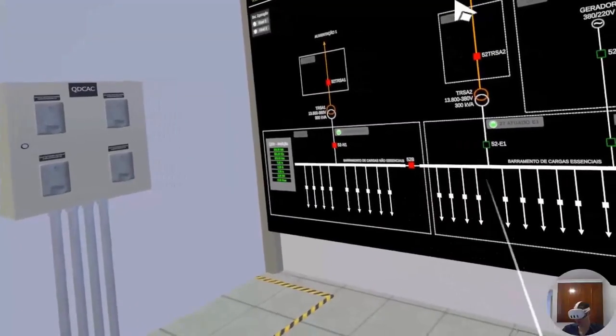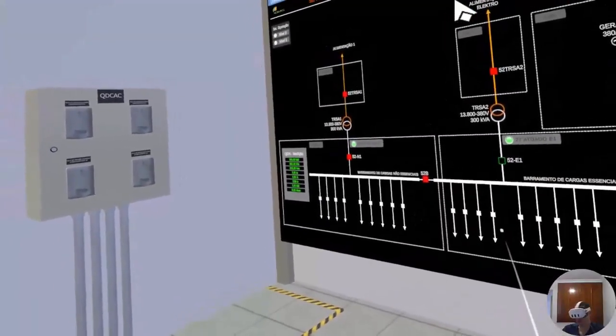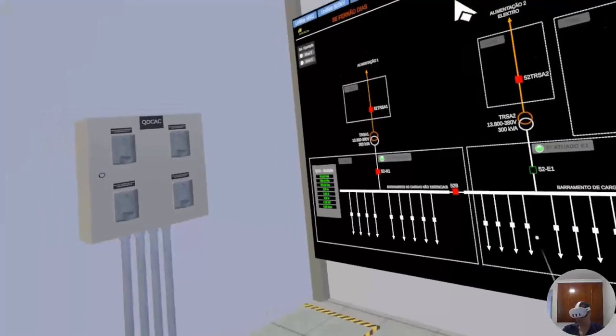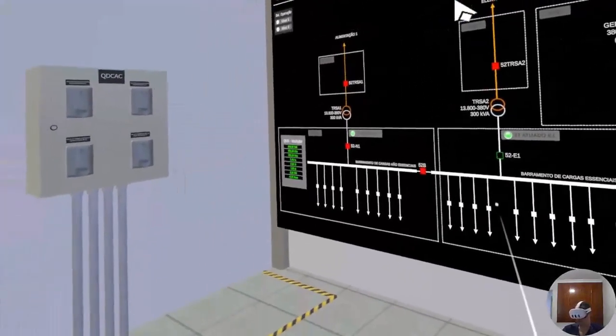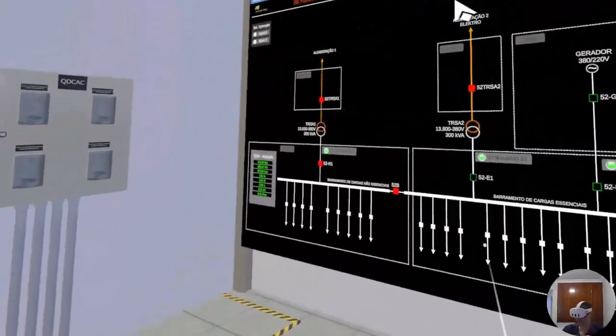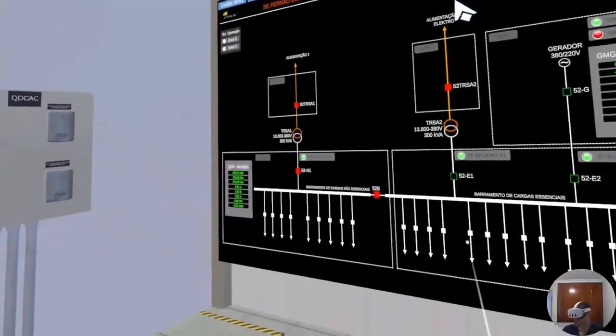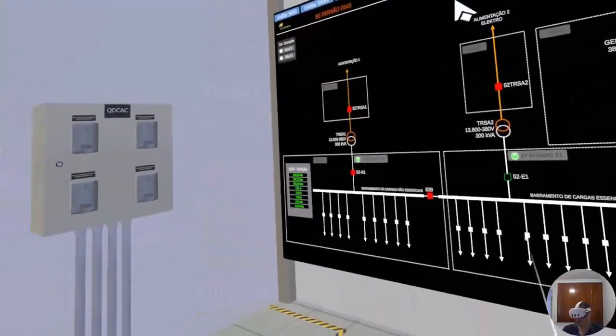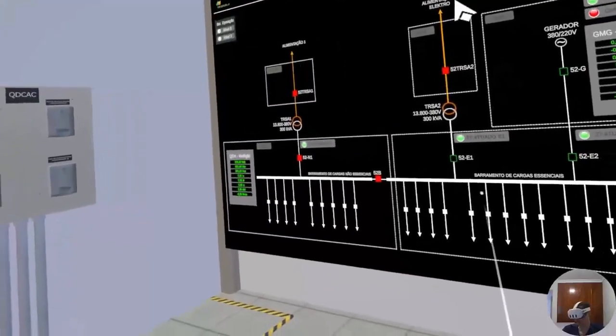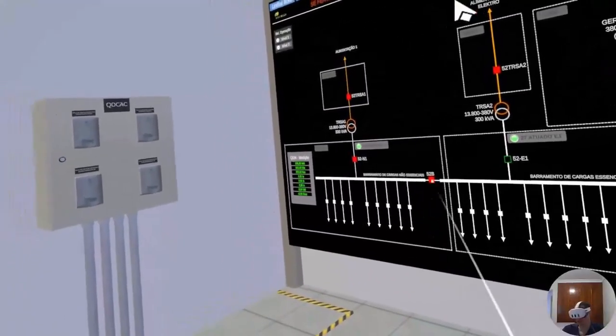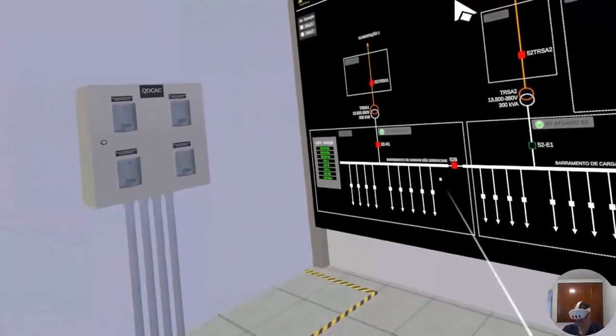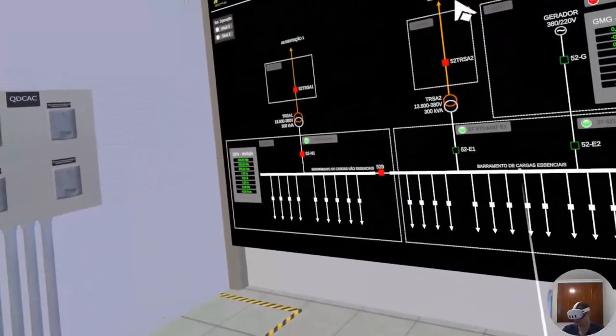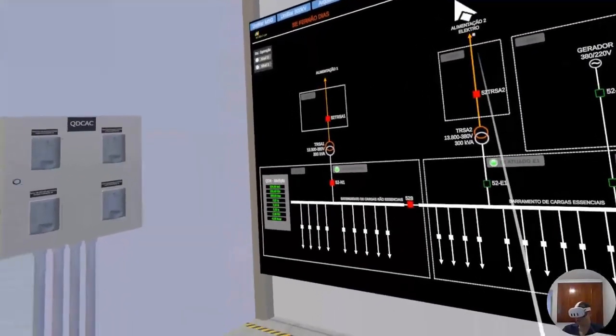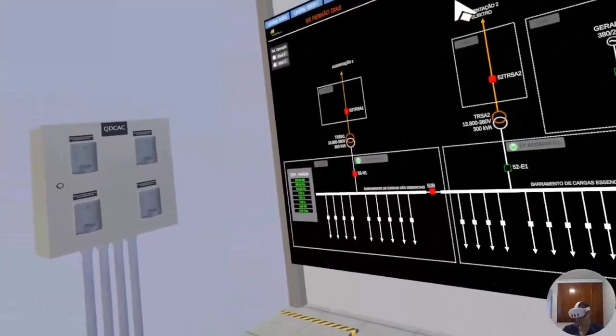Because when we lose the power supplies, all the AC equipment will shut down, except for those connected to the inverters. The inverters are connected to the battery bank, so those won't shut down. But the loads that are connected here to these two bus bars will shut down. And the loads are divided into non-essential and essential. So since I have a strong source here, I'll simply open this one and close this one.